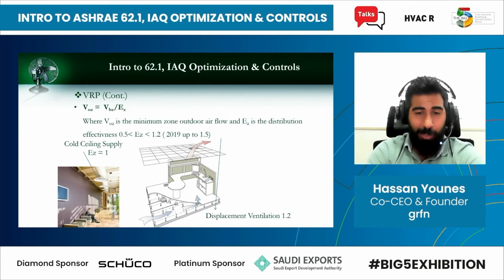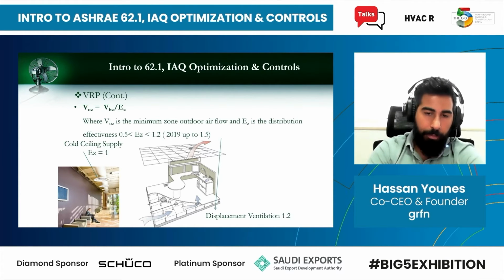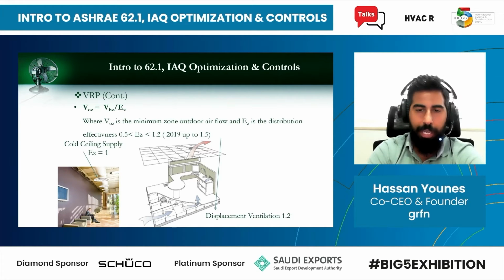If you have, let's say, displacement ventilation, you divide by 1.2, so you actually decrease the amount of required outside air, because the displacement ventilation method can help in reducing the contaminants by picking them up from the floor up to the exhaust, and thus you get a better figure and a lower amount of outside air as required.